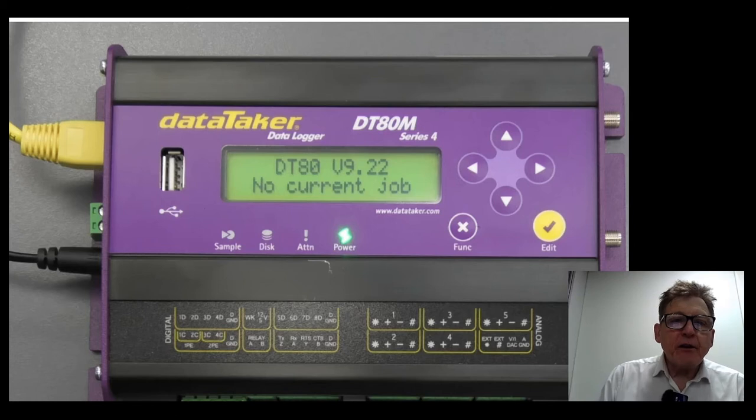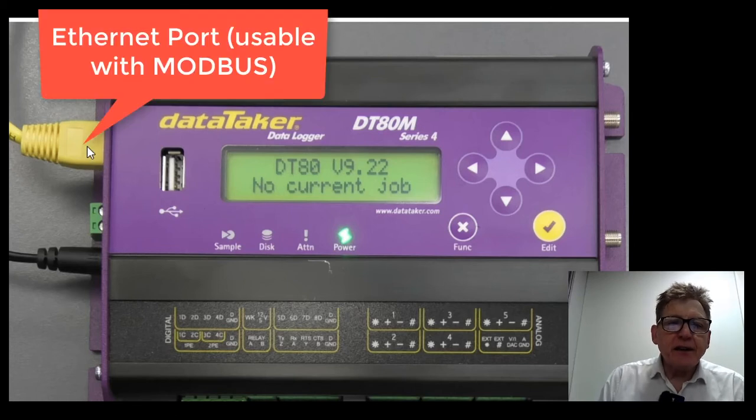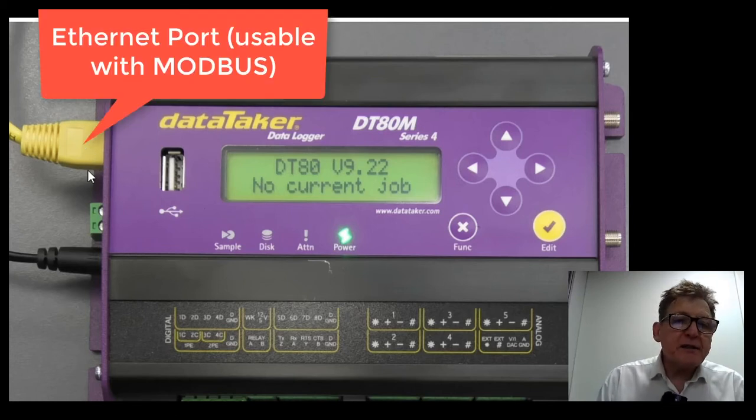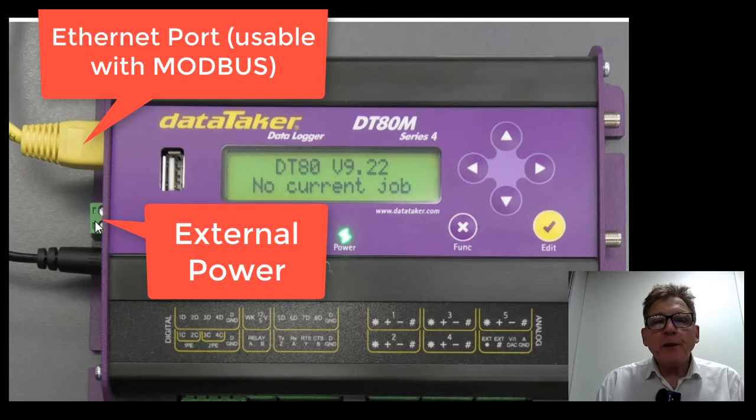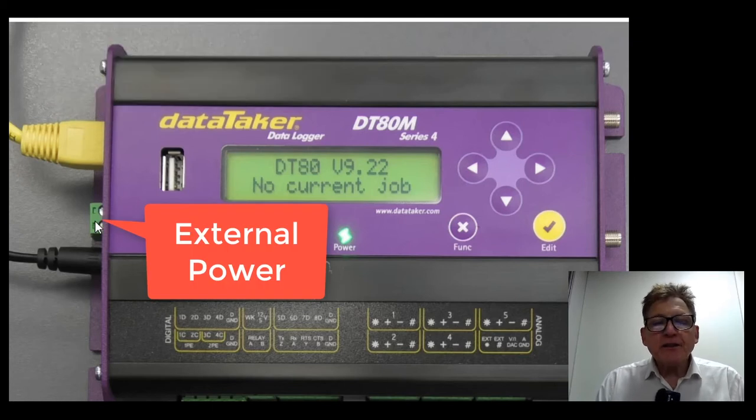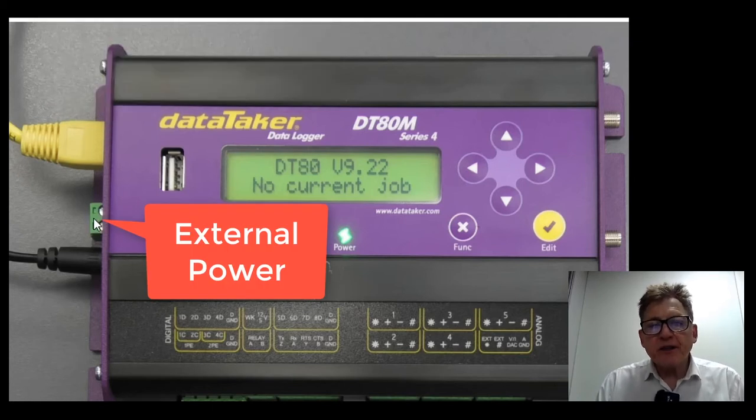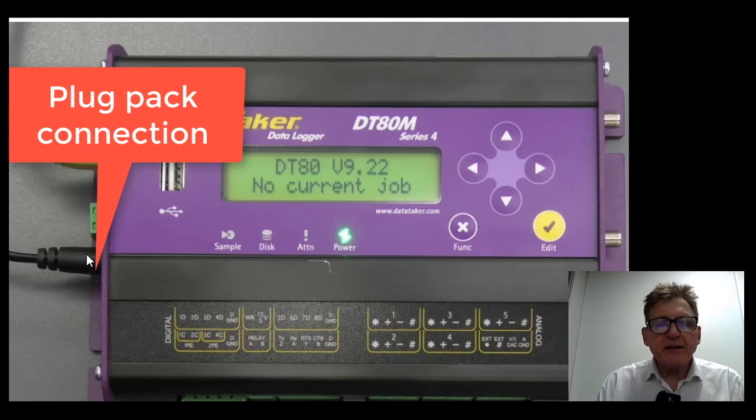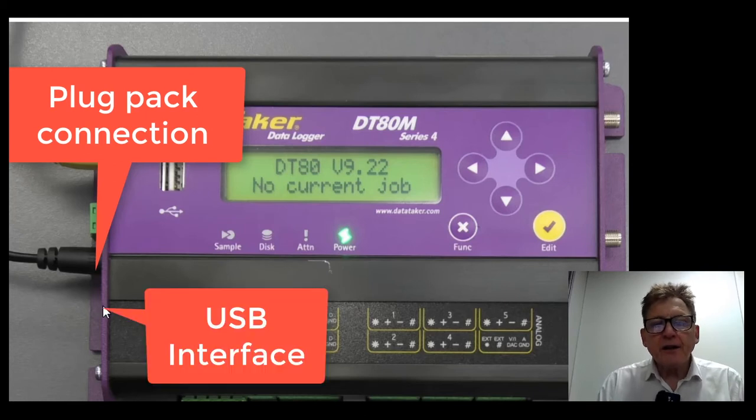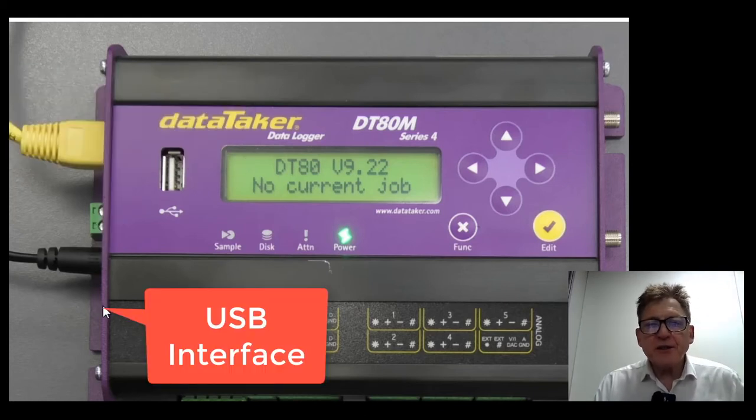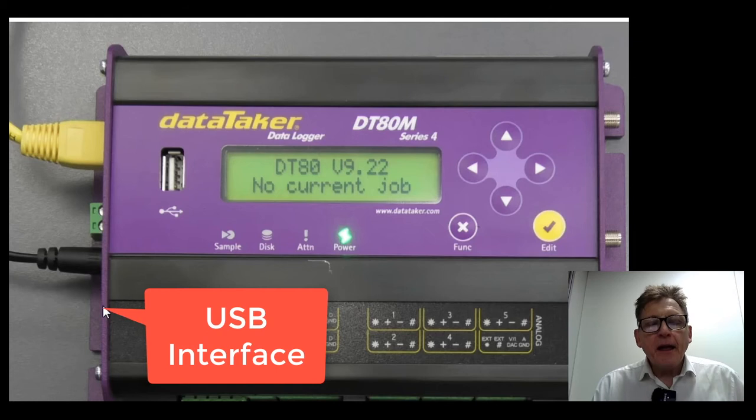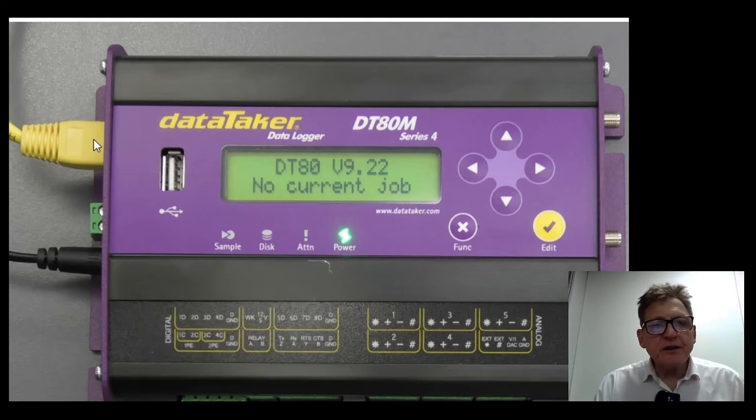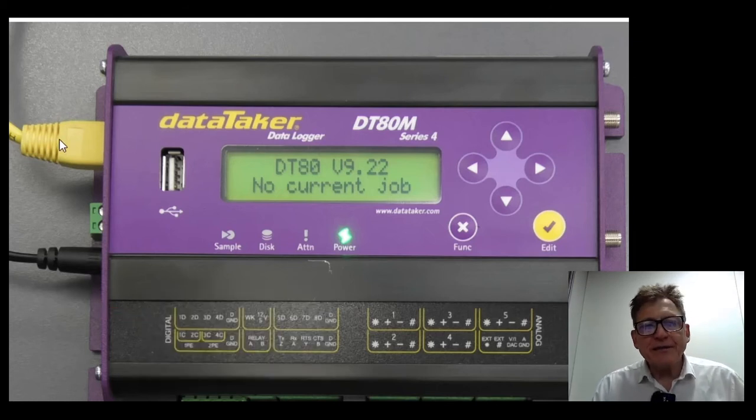We'll quickly go over some of the features. It has an Ethernet port which also supports Modbus, external power. We will normally be supplying this with an external battery, this is a plug pack that's come in here. There's also a USB port for connecting to your PC. It's usually easier to connect to the device using Ethernet.